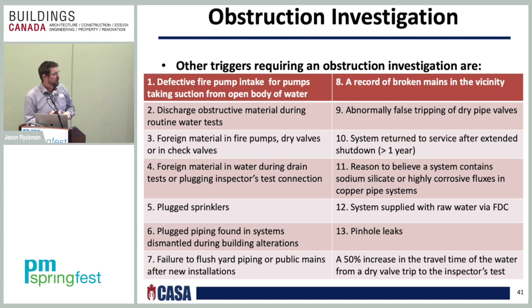Also, one of the key things, if you have a dry system and you have a 50% increase in travel time or delivery time from your acceptance test of your dry system, and it's 50% more time to get from the valve to your most remote outlet, that would be a means of obstruction investigation. That means something's going on in your dry system that's obstructing the air from getting out of the system to get water to the system.